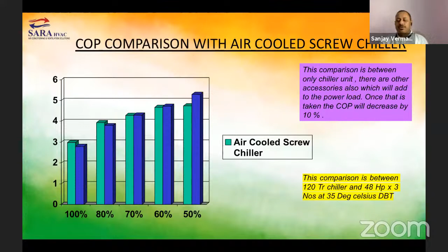This comparison is made for 120 TR chillers and again 48 HP into 3 numbers of VRF systems combination at 35 degrees Celsius DBT outside. And this comparison is between only the chiller unit. There are other accessories which are not added here. The chiller will be having the pump, the cooling towers, and many other things. That calculation is not added here. Once that is taken, the COP will decrease for the chillers by 10%. It means the COP for our VRF systems will be much higher as compared to screw chillers based on this performance chart.